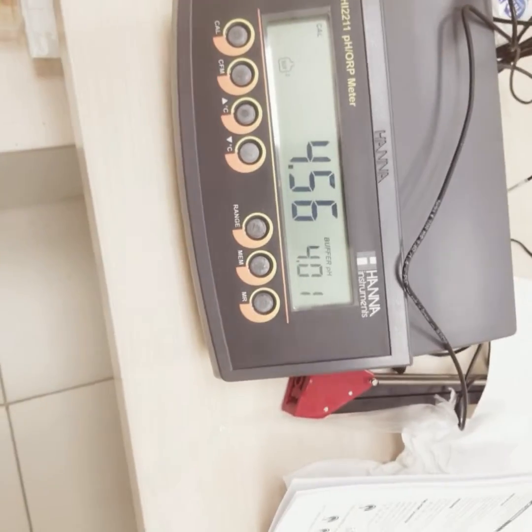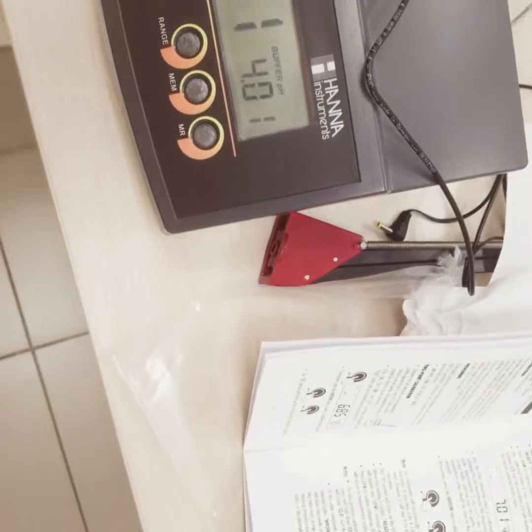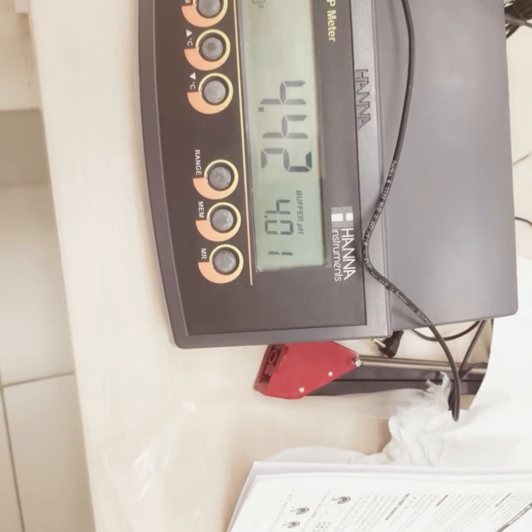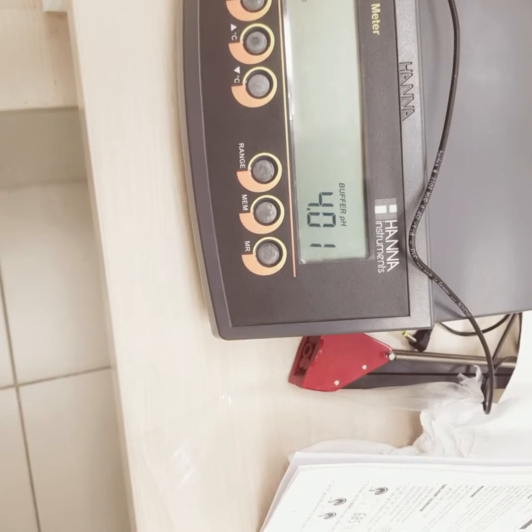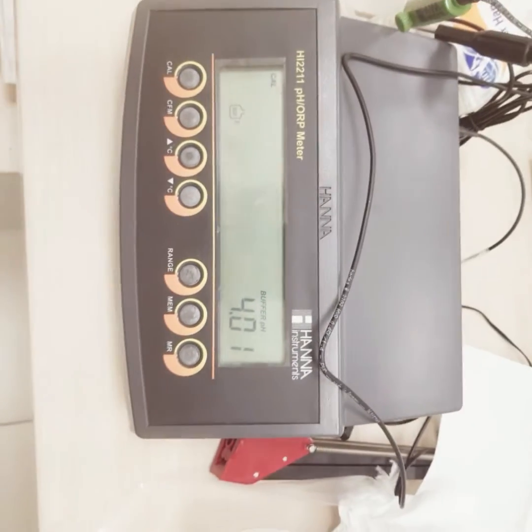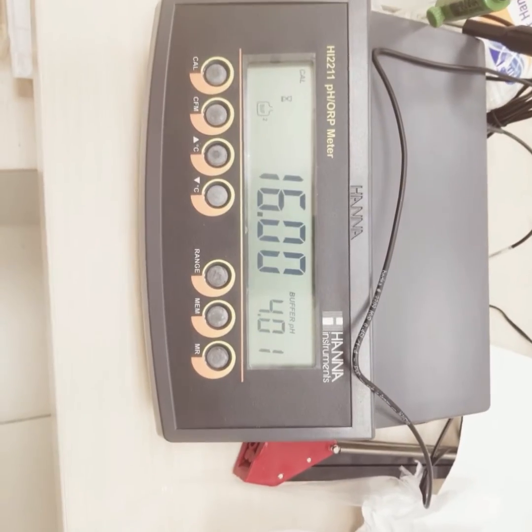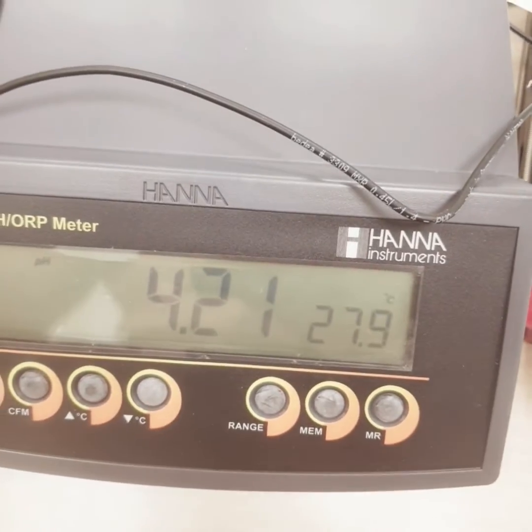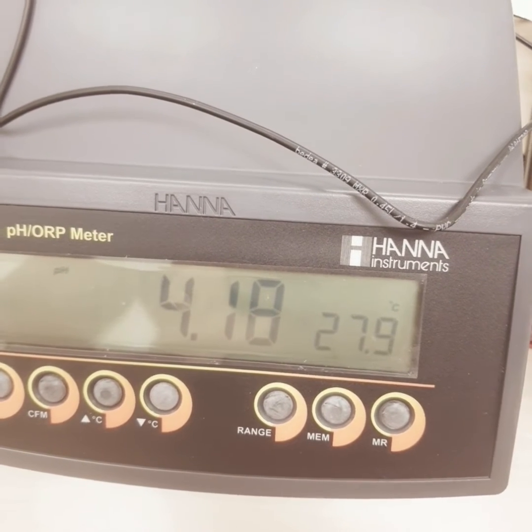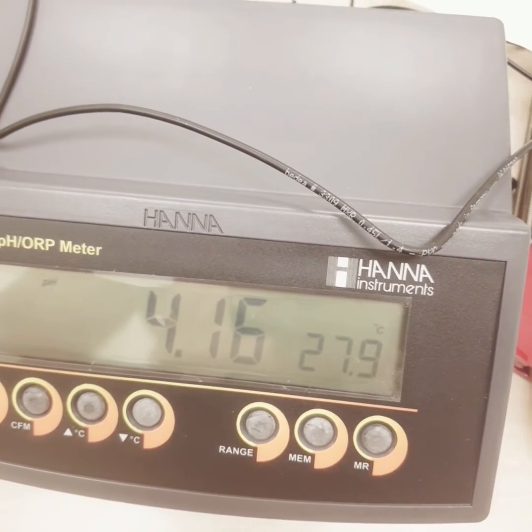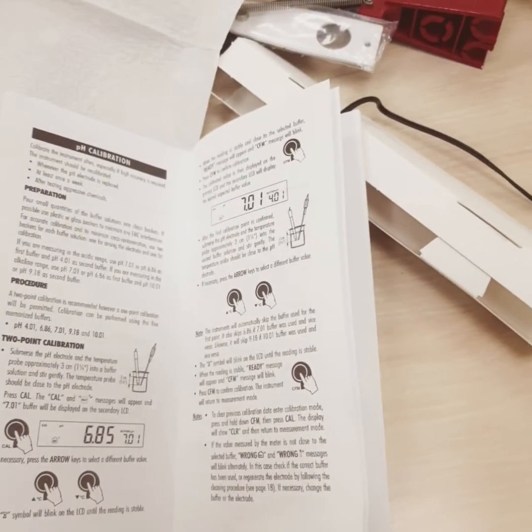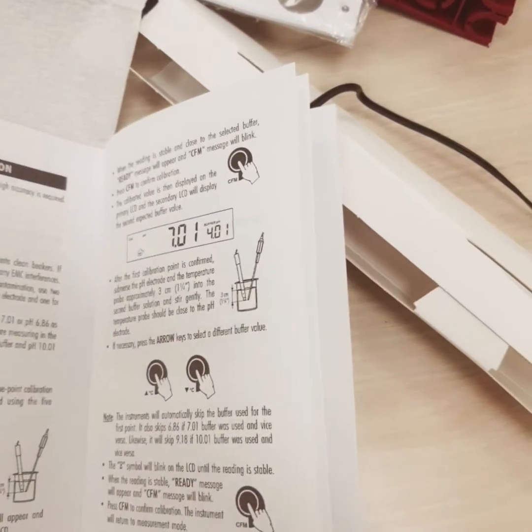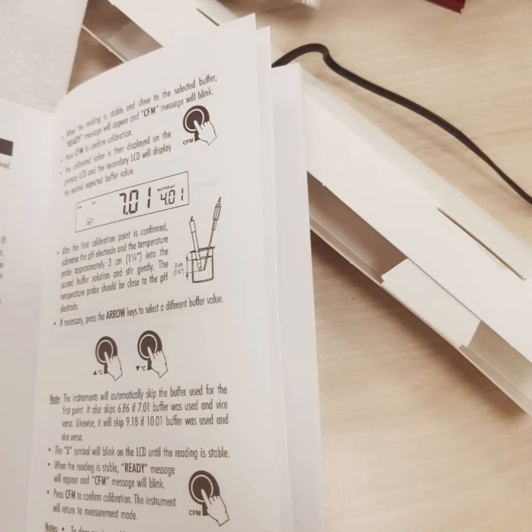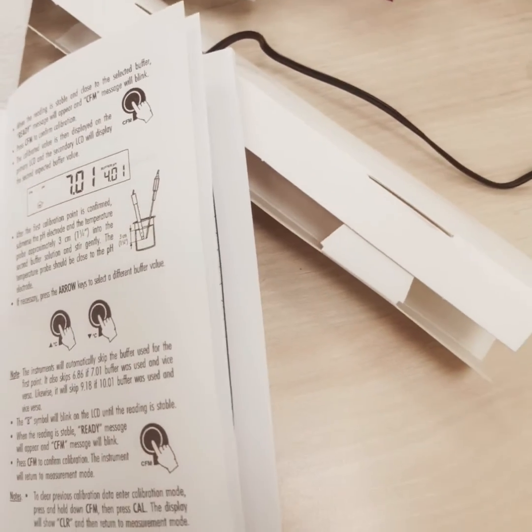Now I have transferred the pH 4 buffer. And also we just shake this. So usually the preferable way is to add it to the hot plate and keep the beads. Guys, we achieved the calibration. So you can see the pH 4 shows 4.19, which is close to 4. Okay, and also here in the calibration, usually the two probes should be close to each other, the temperature probe and the pH meter probe. So this is all about the calibration of the Hanna instrument pH meter.